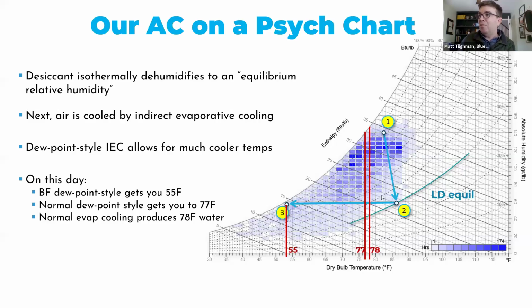So this kind of explains why we can run the conditioner without electricity to do true comfort cooling: we can get the air temperatures down to the 55 Fahrenheit that the air conditioners expect, because we pre-dry the air with desiccant. And that's also a temperature that is much more useful for data centers too. So they don't have to avoid running their evaporative coolers, or they don't have to have a chiller alongside their evaporative coolers for the humid days.